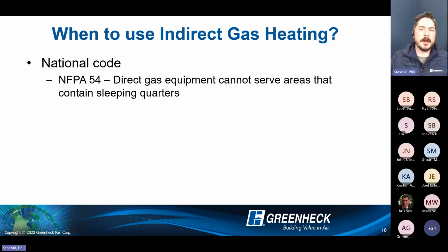So when do we actually use indirect gas fired heat? Direct gas, if we're talking gas in general, is definitely the one that makes sense. But indirect exists really for this: under NFPA 54, direct gas equipment cannot serve areas that contain sleeping quarters, anything defined as sleeping quarters or a dwelling. But not many makeup air applications actually fall under this category. So we picture makeup air, picture wastewater treatment plants, general manufacturing, warehouses, kitchens. Not many of them can be defined as a sleeping quarters. So in most makeup air applications, if you have access to gas, direct gas really should be the forefront one to consider.